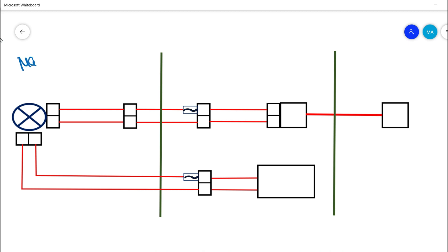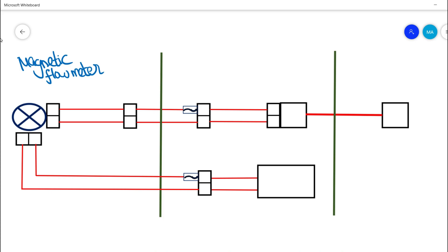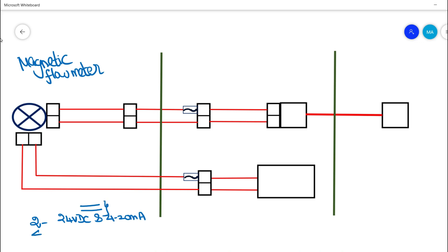This is basically a magnetic flow meter, and magnetic flow meters come in 4-wire loop configurations. So what is basically 2-wire and 4-wire? In a 2-wire system, 24 volt DC power supply and 4 to 20 milliamps signal would be running in just 2 wires. This is basically the 2-wire system.